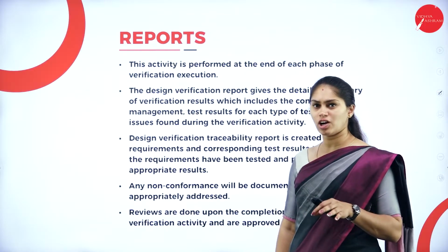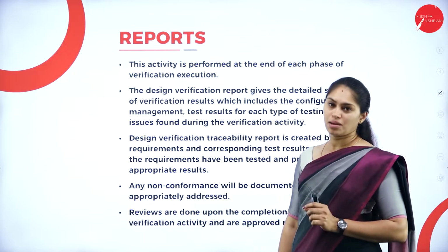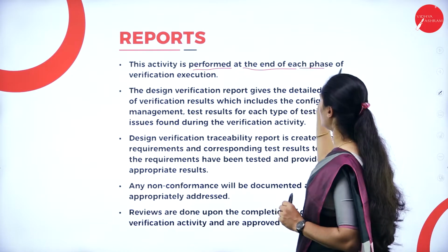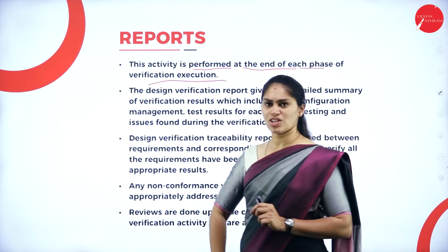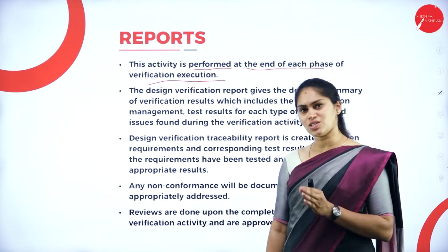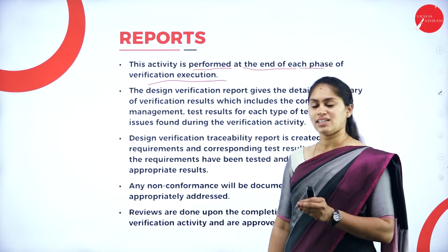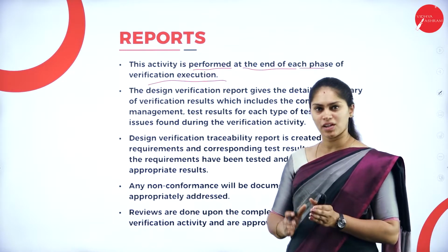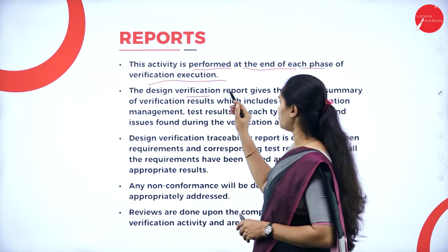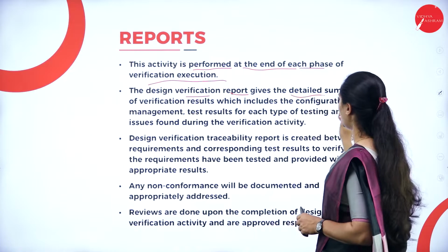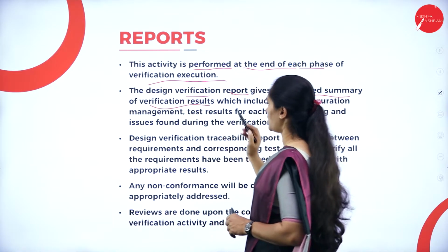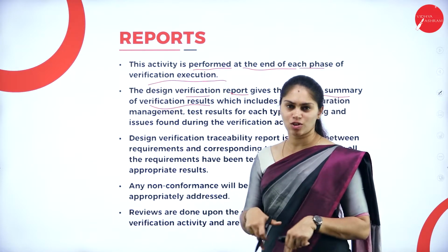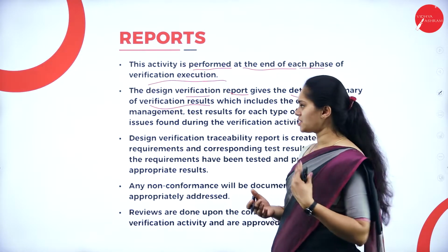Now the execution is over, and then we must have a report. The reporting activity is performed at the end of each phase of verification execution. At the end of each execution phase, that needs to be reported or saved as a document. The design verification report gives us a detailed summary of the verification results. It's like a medical report. It gives you complete details of a particular test that you have taken.